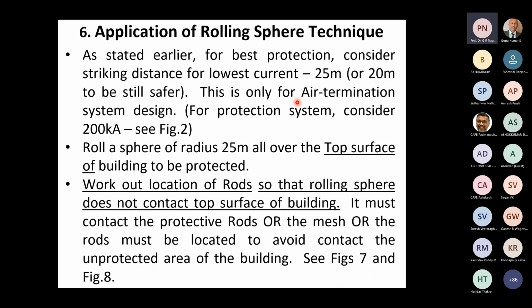I will repeat it. The lowest current that is seen is about 5 kiloamperes, for which the striking distance is 20, taken as 25 meters to be safer, or even 20 meters if you would like to be safer. Then roll the sphere of radius 25 meters all over the top surface of the building to be protected. Work out the location of the rods so that the rolling sphere does not come into contact with the top surface of the building. It must contact either the tips of the protective rods or the mesh, or the rods must be so located as to avoid contact with the unprotected area of the building.